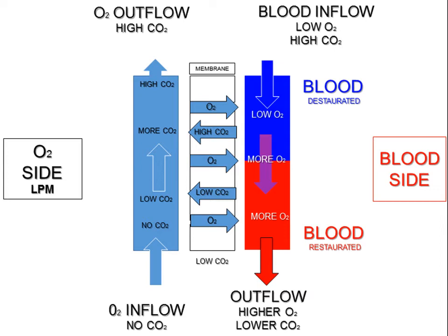On the opposite side of the membrane, on the blood side, you've got blood inflow, which is low in oxygen and high in carbon dioxide. As it goes through, the oxygen is lower, more oxygen, so outflow is higher, carbon dioxide is lower. When you look at the membrane in between, you can see the exchange. Oxygen goes into the blood, carbon dioxide goes out, and it's constantly exchanged. That's basically how the diffuser works.